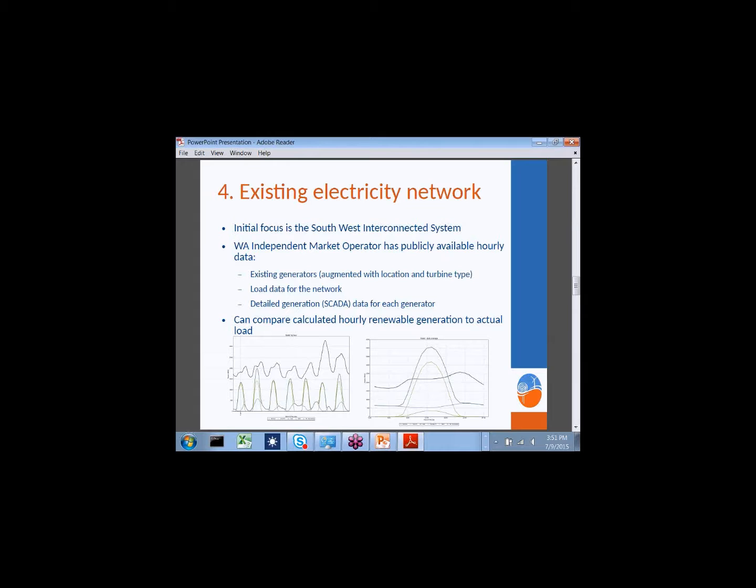The fourth requirement is the existing electricity network. Our focus is the South West Interconnected System. The independent market operator publicly provides data on existing generators—predominantly fossil, but with some wind and PV—load data for the network, and detailed generation data for each generator. We can compare calculated renewable generation to actual load. The small graph on the left shows the top black line representing load for the first week of 2014, and the dark green line is potential renewable generation from a simulated scenario of existing plus additional stations, showing a predominance of solar with peaks during the middle of the day.